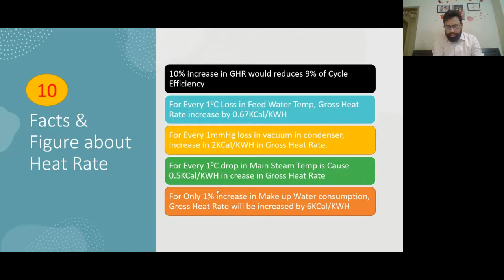So a 10% increase in the gross heat rate reduces the cycle efficiency by 9%. If we lose 1 degree in the feed water temperature, the gross heat rate increases by 0.67 kilocalorie. Similarly for the vacuum, many participants have asked at what minimum value of delta T we can proceed. Definitely, if we can go up to the maximum achievable vacuum, we can speak about the vacuum efficiency. But we know we cannot go beyond 760 millimeter of mercury. So according to that, I have calculated and found that if I lose 1 mm of Hg, the impact on gross heat rate is 2 kilocalorie.